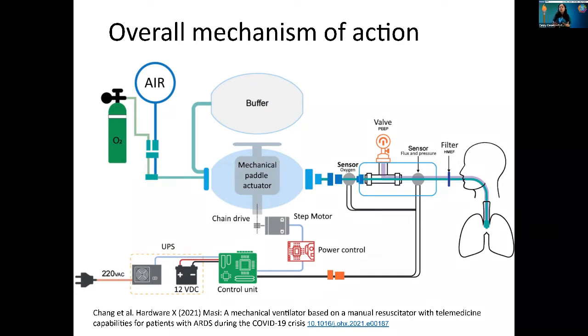So how this started was based on some academic exercises that were previously described in order to generate a new mechanism of action where, as you can see here, a mechanical paddle actuator would press on a resuscitation bag, and this bag would be filled with oxygen coming directly from a bottle of oxygen. And this was really important for us because the flows that usually come from bottles of oxygen are a little bit lower than what you would get from the lines that are usually present in hospitals. So we didn't have those lines. The best option that we had was, first of all, to receive oxygen from bottles. Therefore, this ventilator was designed having in mind that the oxygen supply would be limited and that we needed, to the best of our knowledge, to save as much oxygen as possible.